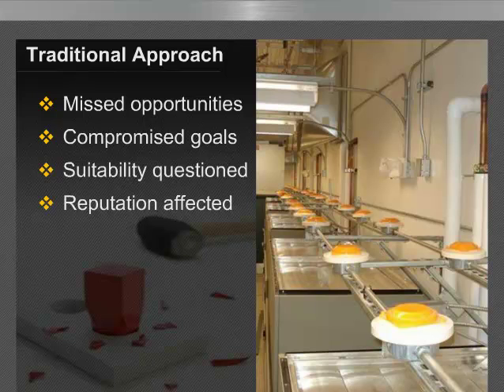We also have some compromised goals. Response objectives are missed. Minimized maintenance opportunities and minimally intrusive access, as we talked about, are missed, given the difficulty of getting to these detectors to maintain, test, or inspect, or getting to the HVAC system to service it. So we have a number of objectives that have been missed. These particular detectors may be challenged in regards to performance and air velocities. The objectives in terms of sensitivity, given a very sensitive classification, which was probably the intent, may be compromised because of how these detectors are installed. We first look at the orientation of the detectors and see that they're upside down, which is outside of the approval or listing. In respect to performance, we can't be certain that it will respond as intended. So suitability is questioned.